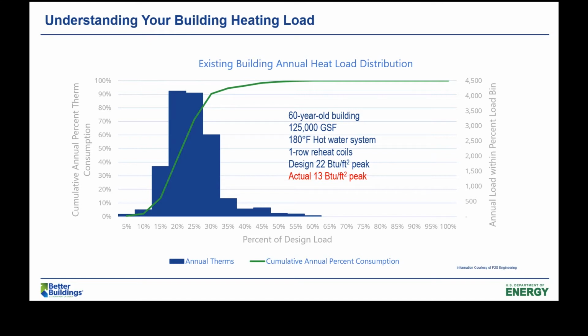One way to think about that is to put in a heat pump that's only good for 1/3 of the design load. You can make that work economically—you'll be running it a lot, and it's not quite as big on your electrical infrastructure. In fact, it might match what you're doing on the cooling side, so it doesn't increase your electrical load, and maybe leave a gas boiler for that last 10%, just to do some of those finishing loads.